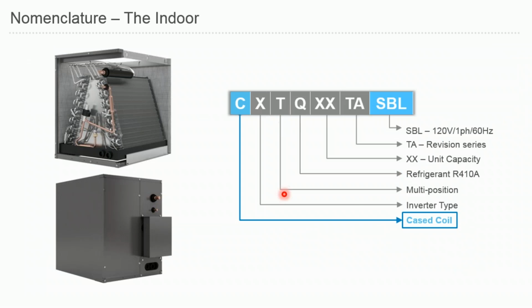So things to keep in mind here on the nomenclature. When you look at the A-coil nomenclature, it's different than your typical VRV indoor unit nomenclature. The smallest capacity is the 2-ton 24 model, and the largest capacity is the 60, 5-ton model. So if you're saying CXTQ 24, you're referring to a 2-ton model. And the other thing you have to look at is the power supply letters that you see at the end of this model number, SBL.